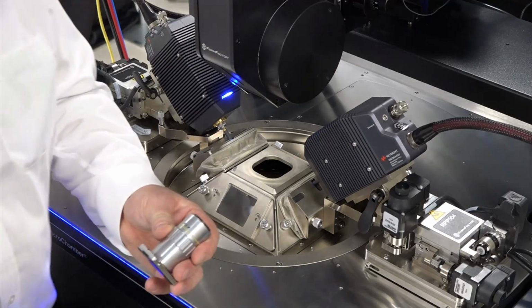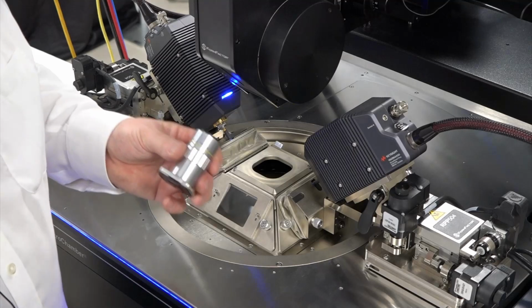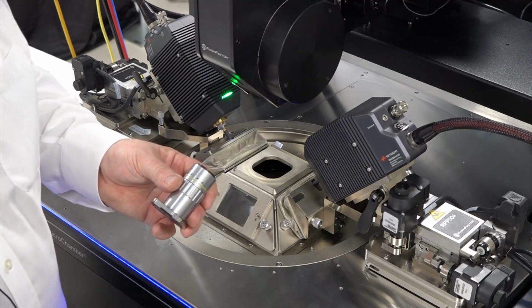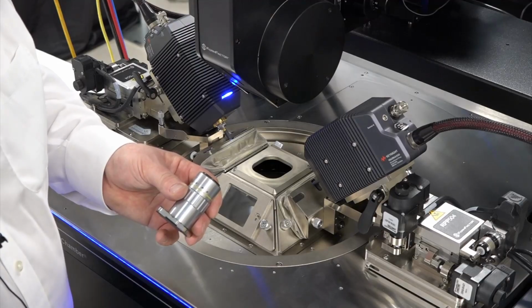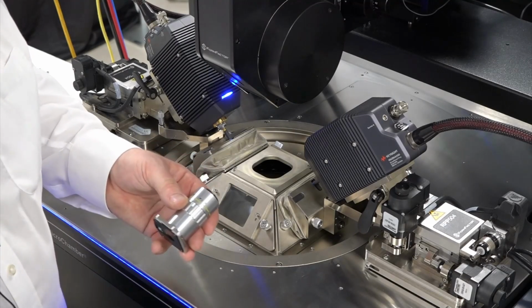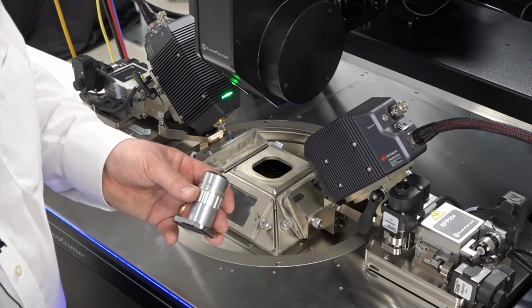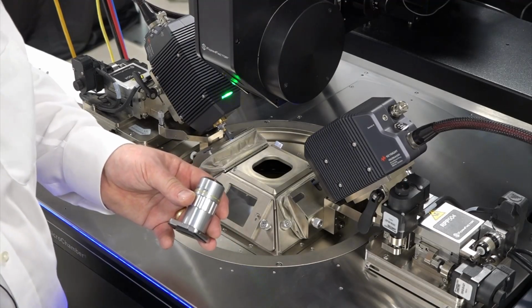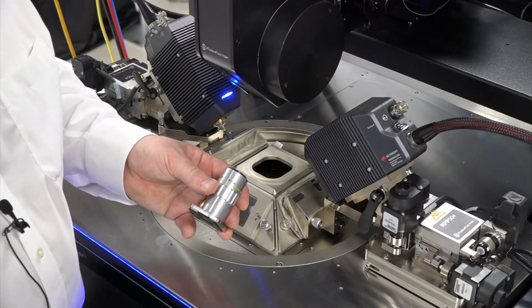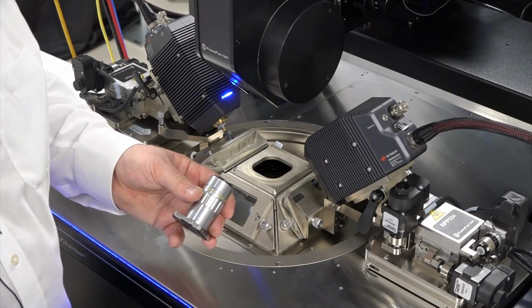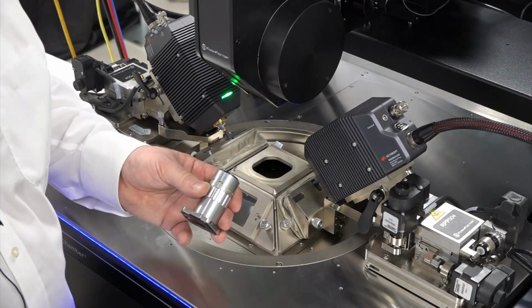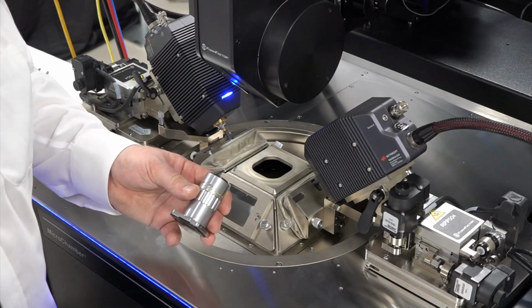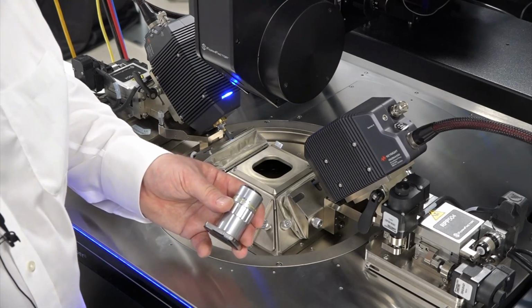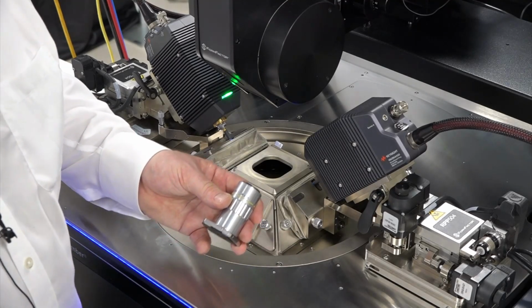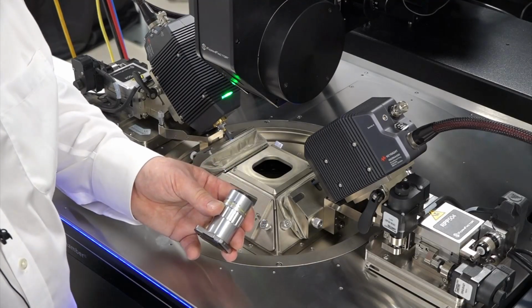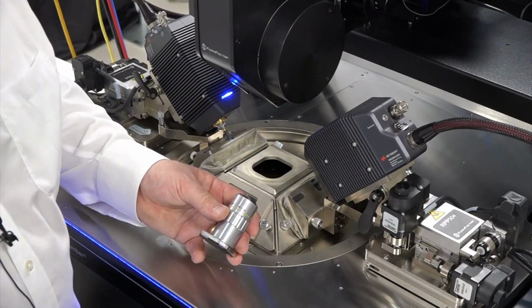So for autonomous, typically I am using a 10x objective for probes like 50 micron, 100 micron. A 20x is very good also, but can sometimes be a little bit awkward because the working distance is quite short. The one point is, if you are using 250 micron probes, you must use a 20x objective. It's down to the fields of view of the E-view and basically the pixel resolution that you get, but the best combination we find for that is to use a 20x objective, so you just need to be a little bit more careful with your objective placement.